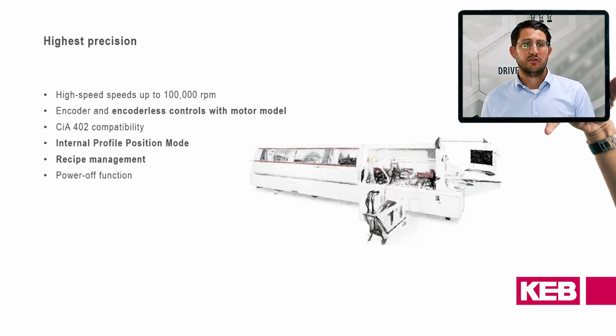We are very dynamic, and the precision and repeat accuracy are the success keys in these applications. Of course, we have various features inside the drive for this application as well, but the highlight, for example, is the encoderless control with motor model. For example, to run a spindle motor up to 2000 Hertz, for drilling or milling a material.